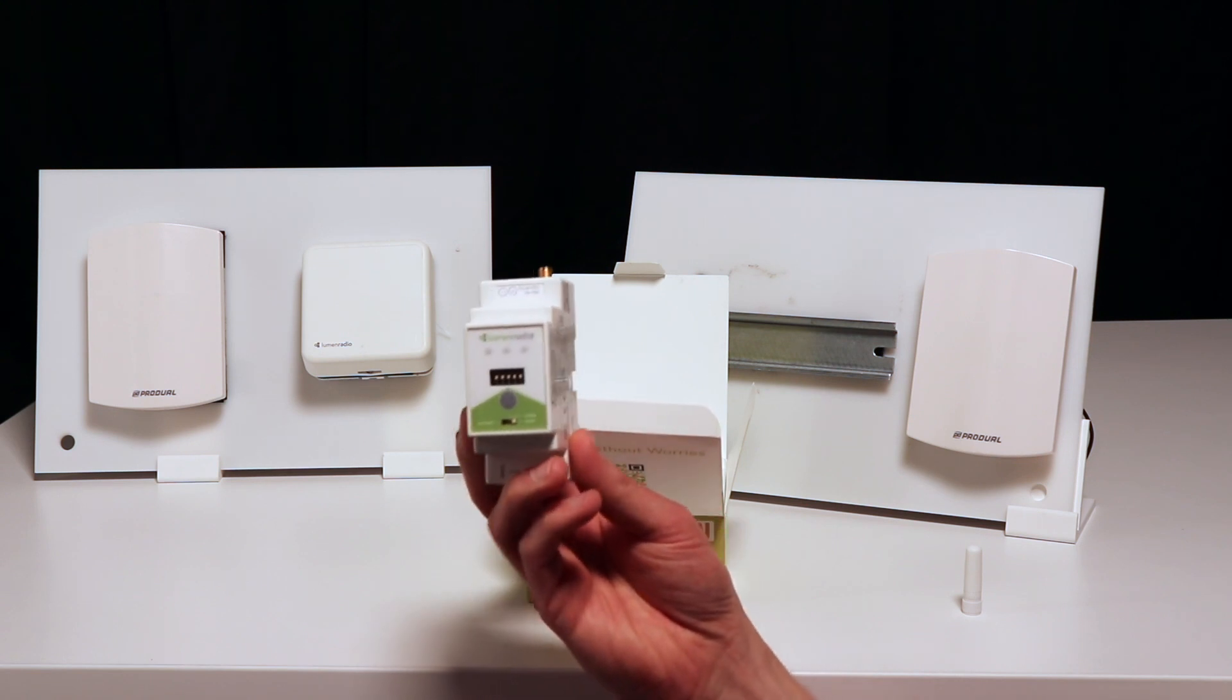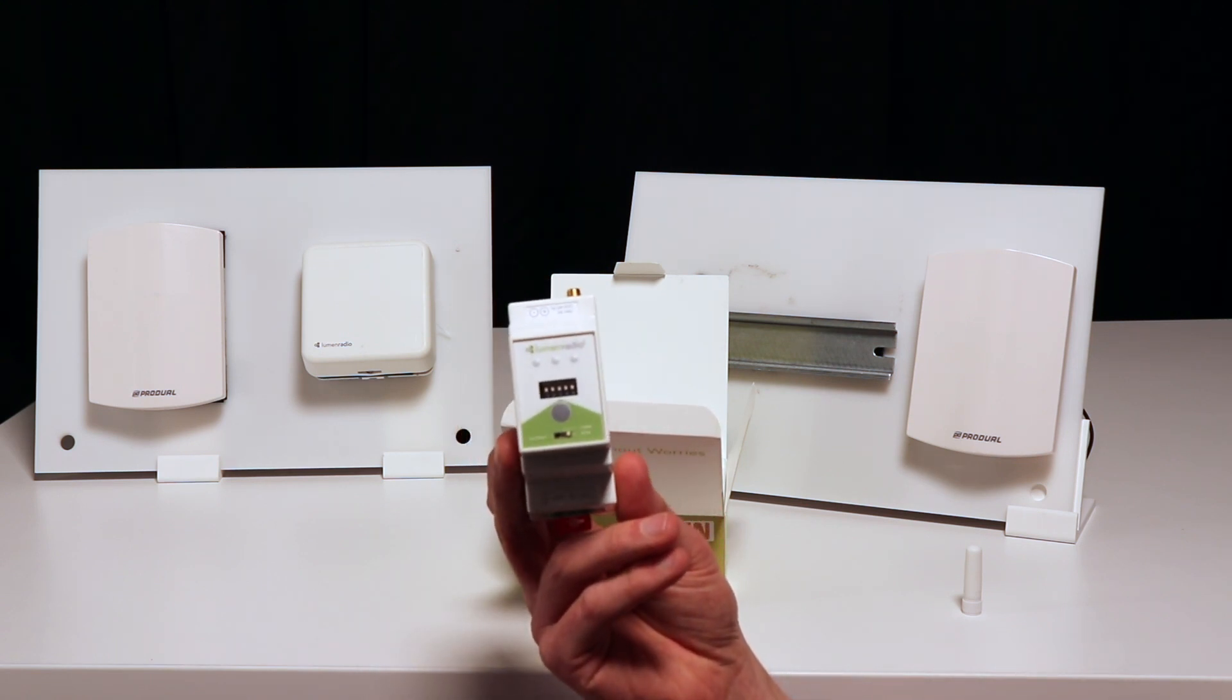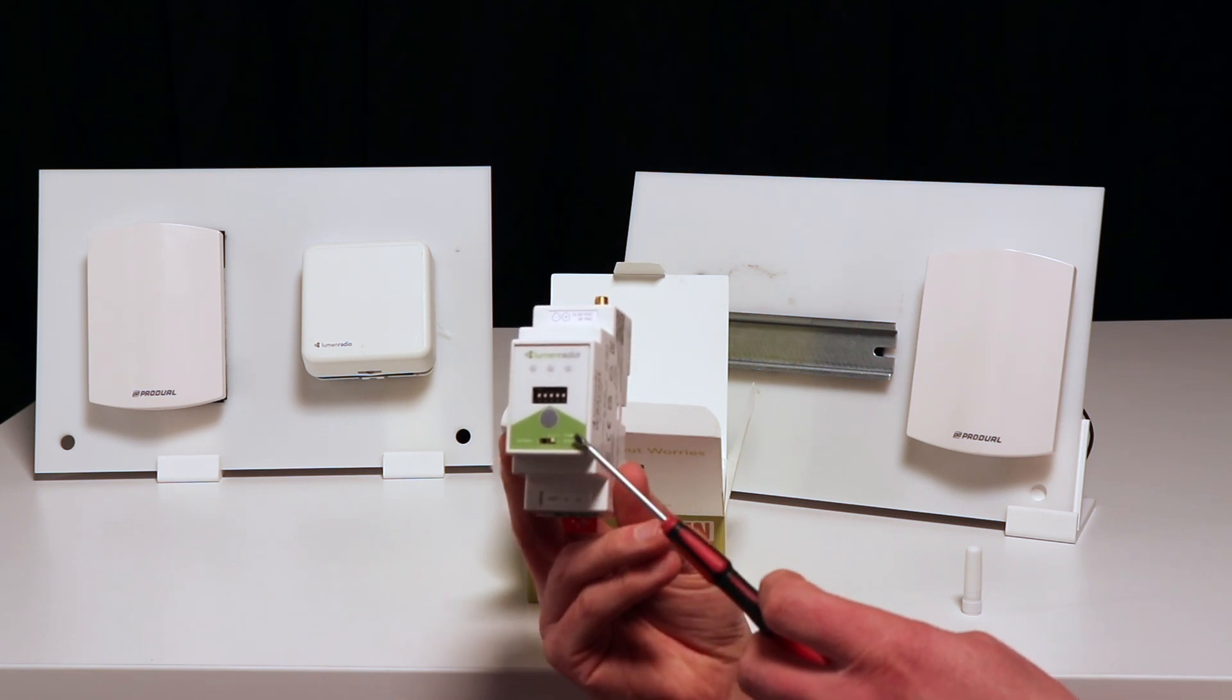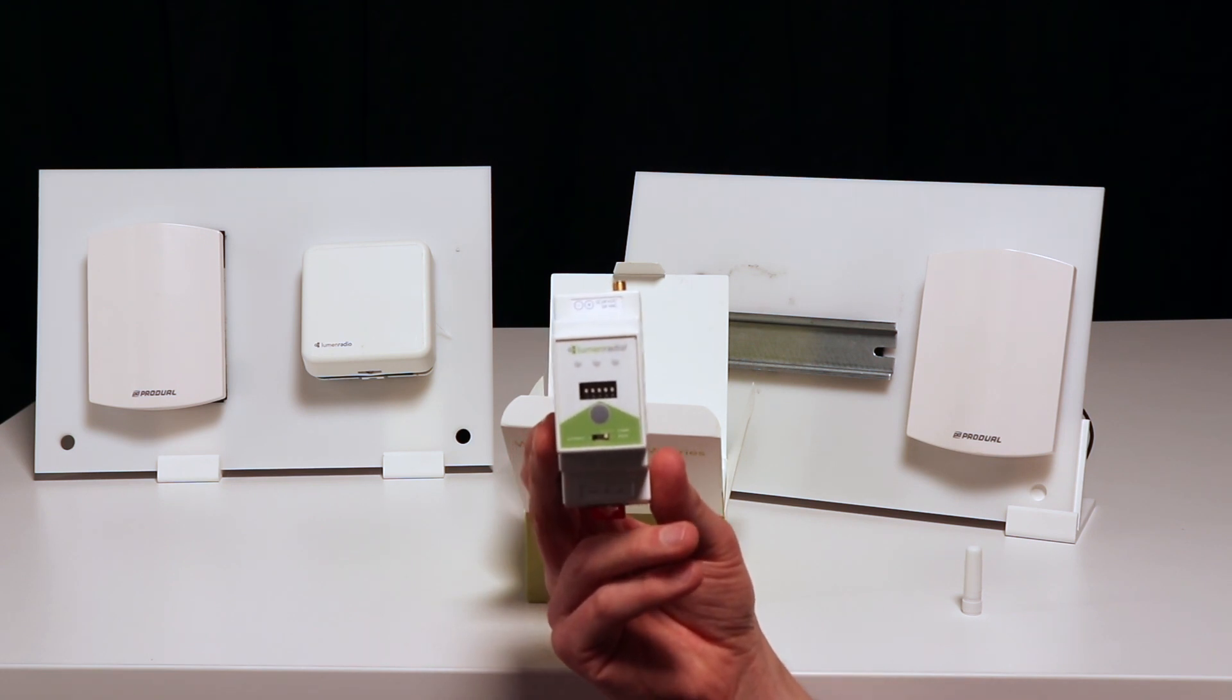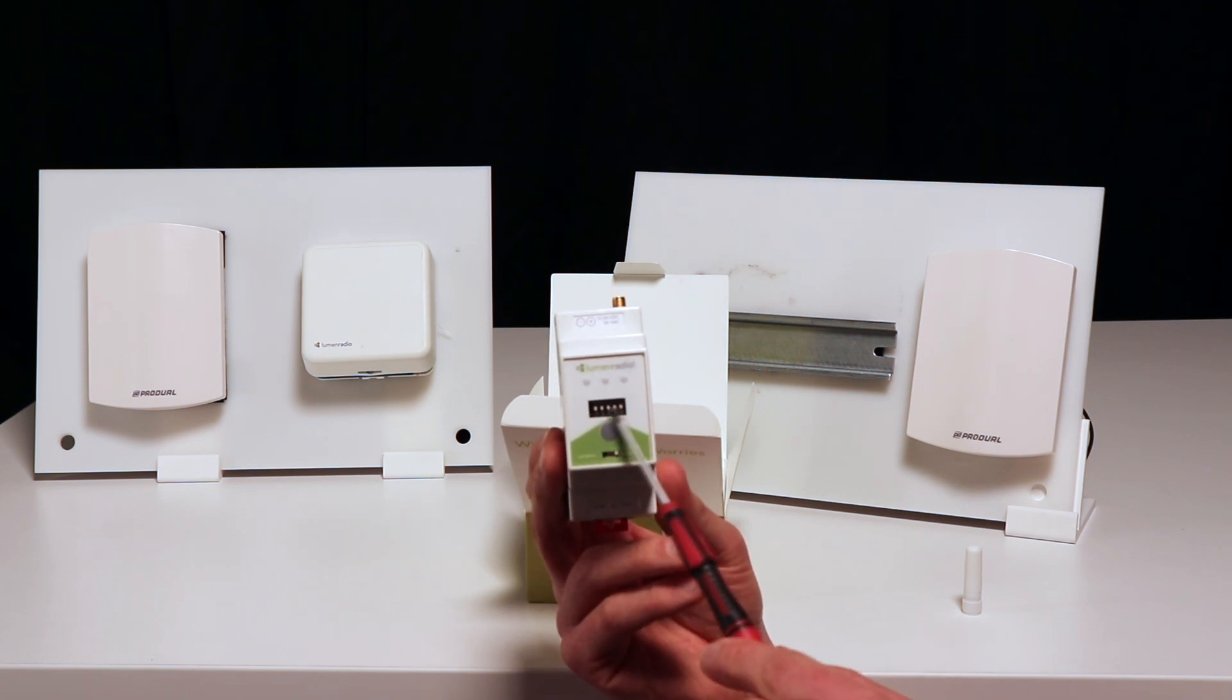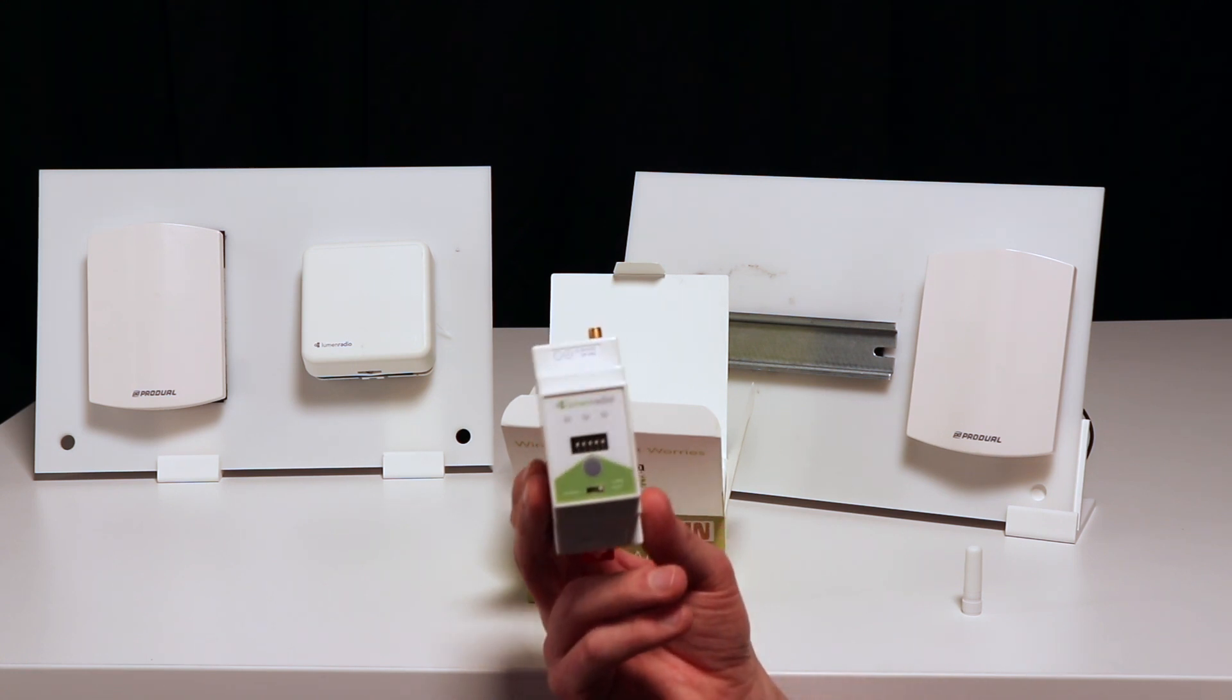The DIN rail as well as the wall mounts will always come with all DIP switches down and the application settings between node and gateway in the node mode. This is the same as the wall mount, so you will have to configure what type of RS-485 you have on the buses as well as if you want to put the DIN rail as your gateway.